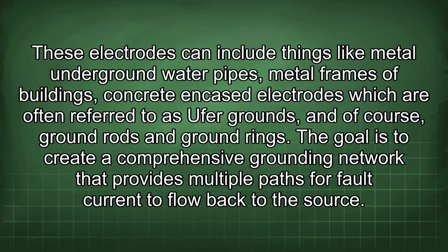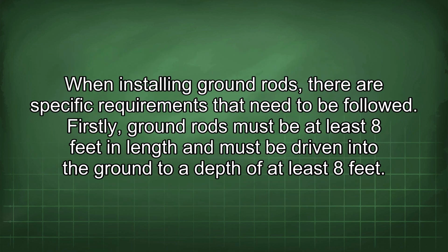These electrodes can include things like metal underground water pipes, metal frames of buildings, concrete encased electrodes, which are often referred to as Ufer grounds, and of course, ground rods and ground rings. The goal is to create a comprehensive grounding network that provides multiple paths for fault current to flow back to the source. When installing ground rods, there are specific requirements that need to be followed.